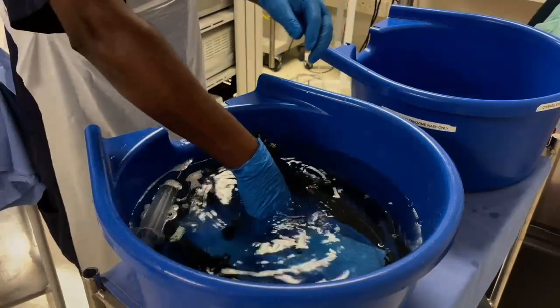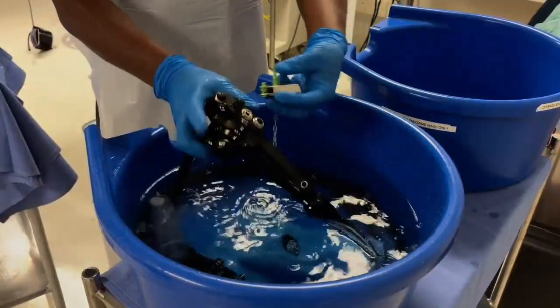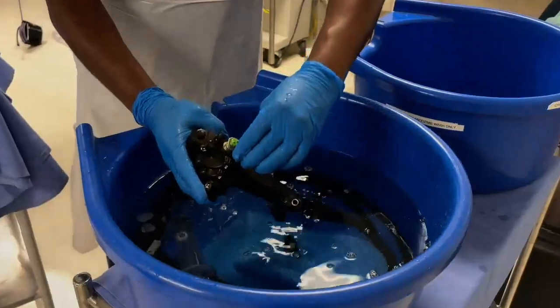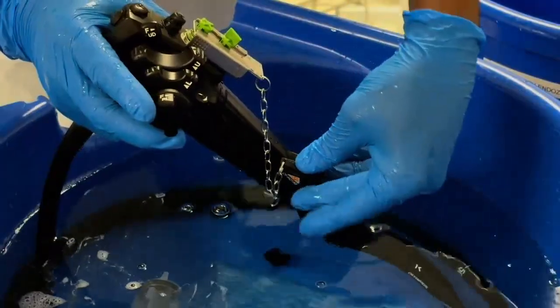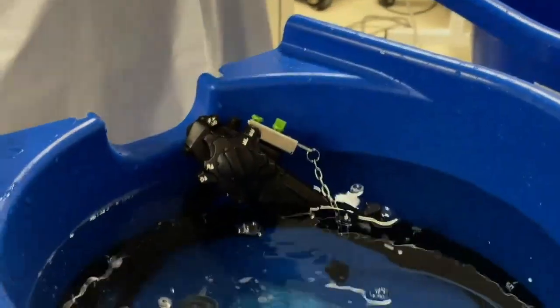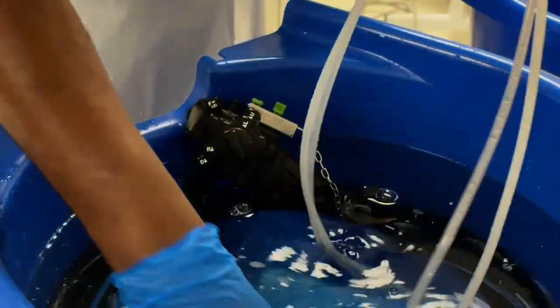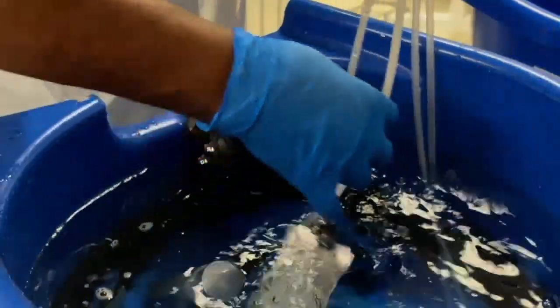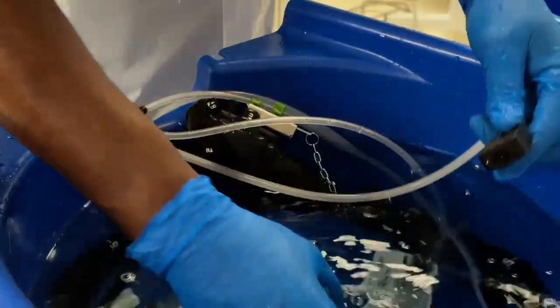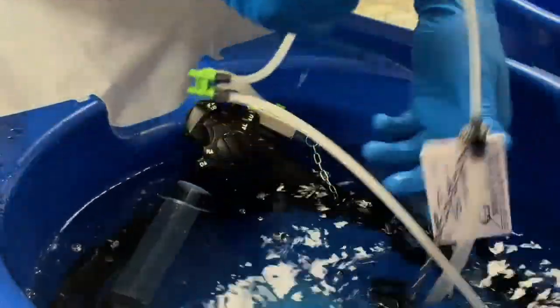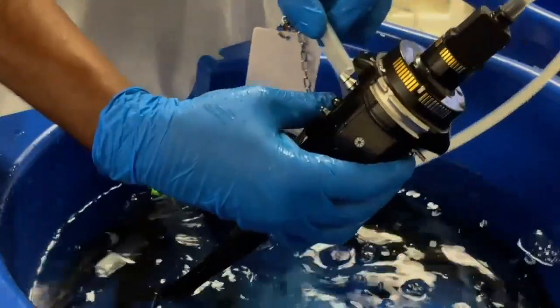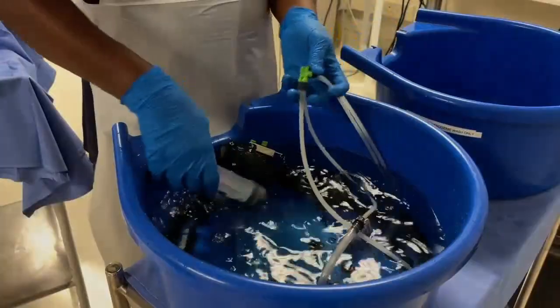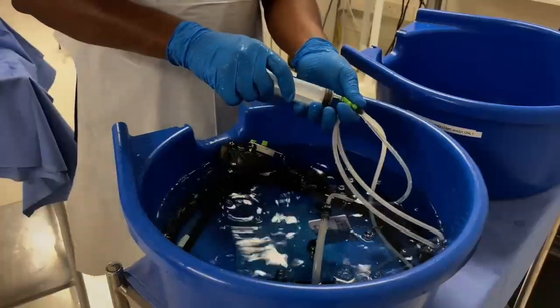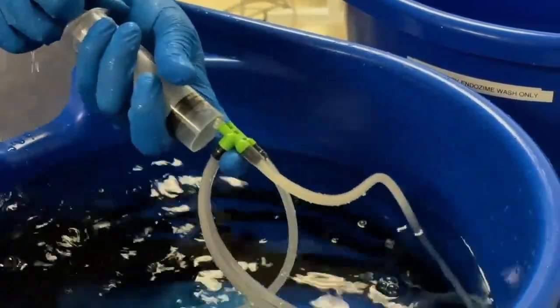The next step in the process is to flush our channels. In this case, of course, we are flushing with the water detergent solution. Begin by applying the adapter seals. The reason for this adapter is that we want to allow for unidirectional flow of the solution. Make sure you have all the correct attachments based on the particular make and model of scope that you have. Apply the connections as directed by the manufacturer, as you have been trained. And ensure that you flush through the right volume of water detergent solution, again as directed in the manufacturer's instructions for use.